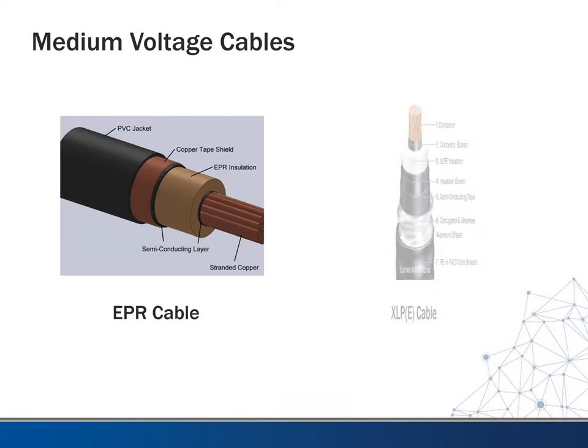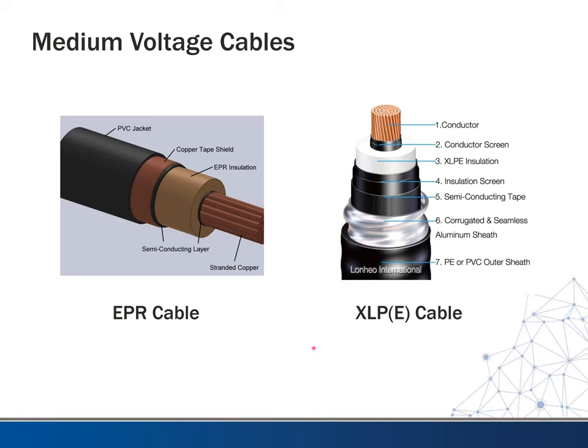Taking a quick look at EPR and XLP cable, you can see these are pretty built up compared to lower voltage wiring. The XLP cable has a conductor, conductor screen, XLP insulation, insulation screen, semi-conducting tape to help dissipate the field, and then usually an aluminum sheath. On the EPR side, it's similar — you have a semi-conducting layer, EPR insulation, copper tape shield, and a PVC jacket rather than a metallic one. You can see this stuff is pretty heavy duty and can be tough to work with.